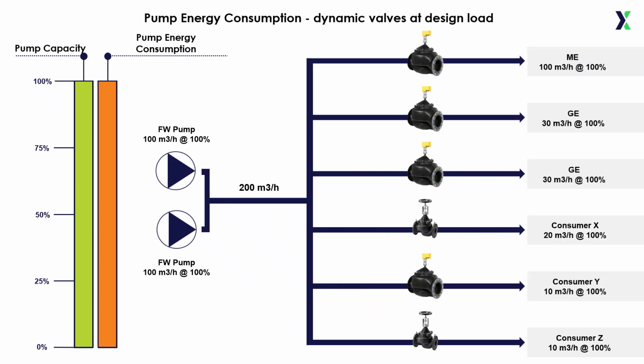In this example, we return to full design load conditions. Two freshwater pumps rated at 100 cubic meters per hour each, supporting the main engine at 100 cubic meters. Two generator engines at 30 cubic meters each, and additional consumers at 20, 10, and 10 cubic meters. This totals a pump capacity of 200 cubic meters per hour.